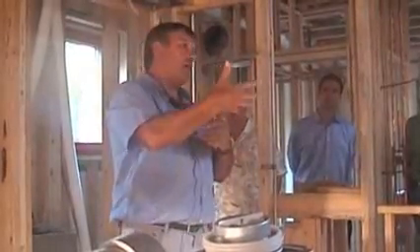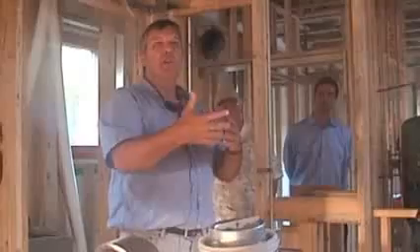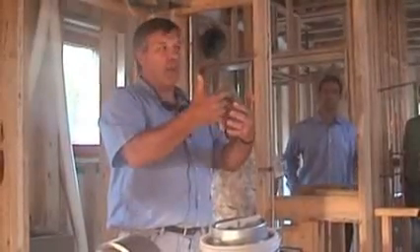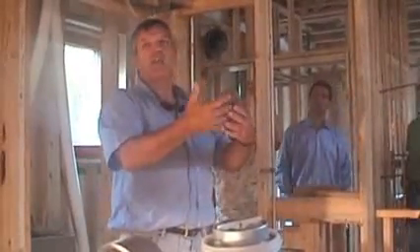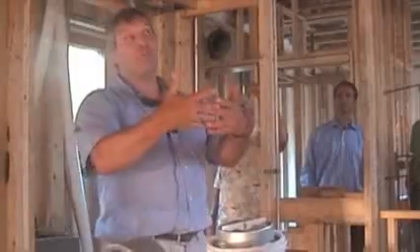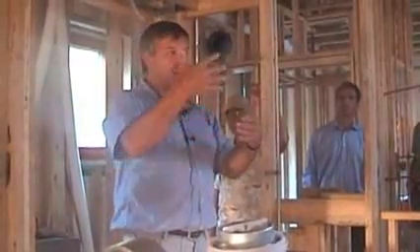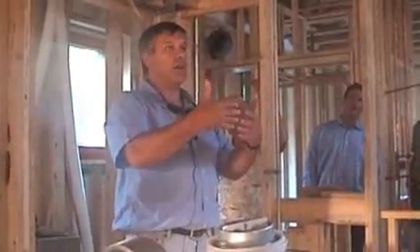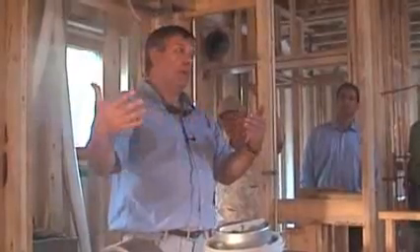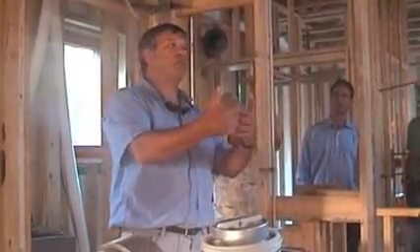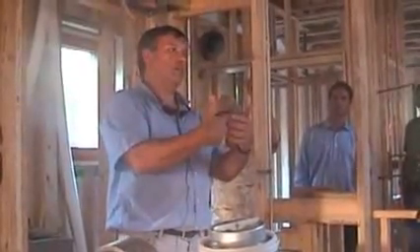It's made out of, in our case, plastic or aluminum, and it's just transferring heat. With an energy recovery ventilator, or enthalpy recovery ventilator, instead of plastic or aluminum on those layers, it's a membrane. And it allows moisture to transfer through it along with heat.